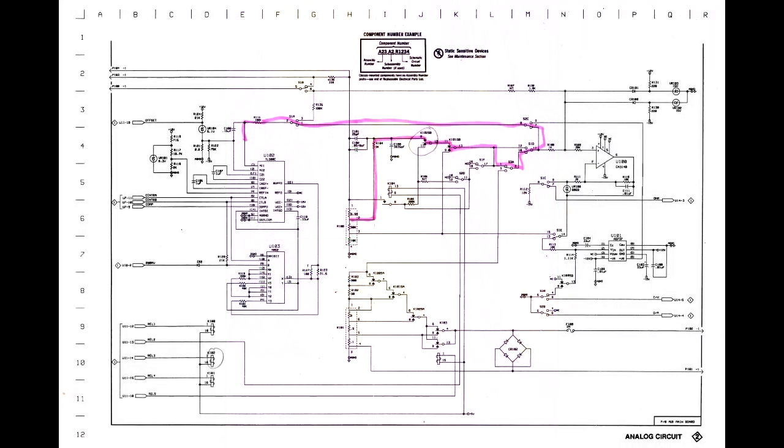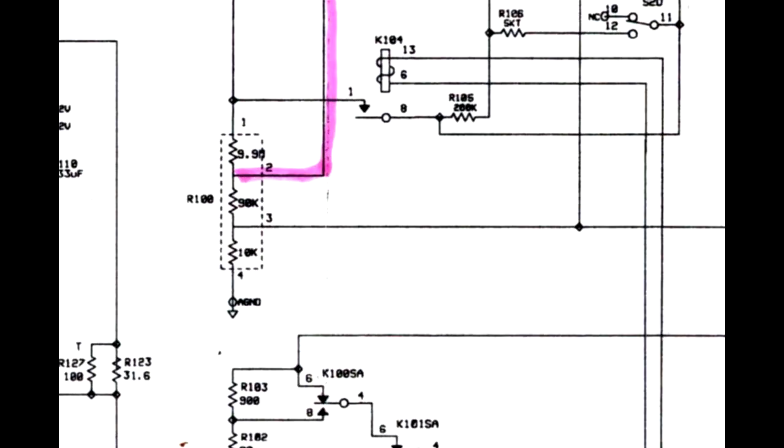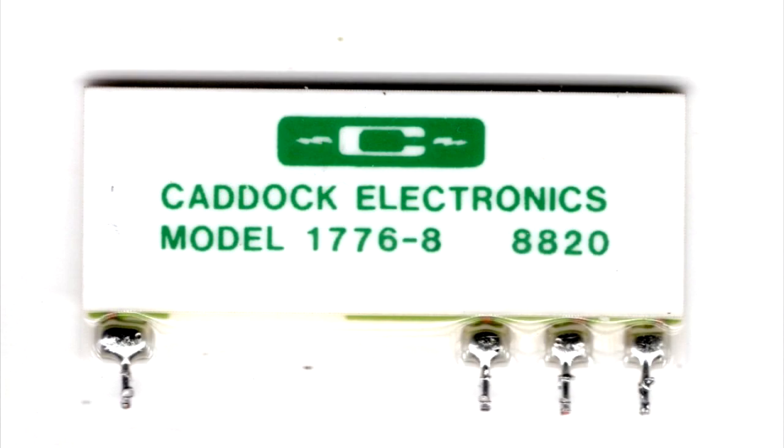The input voltage follows a tortured path through the mode switches and range relays before it reaches the precision divider made by Caddock. Suspecting the divider was drifting with temperature, I removed one from an instrument, bench tested it with the 6.5-digit Keithley, and found no problem.